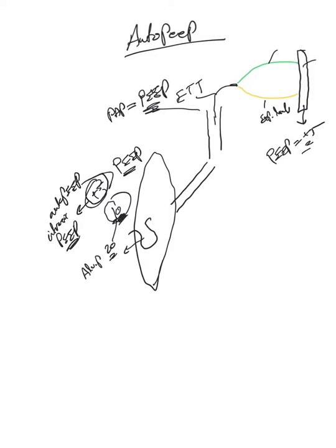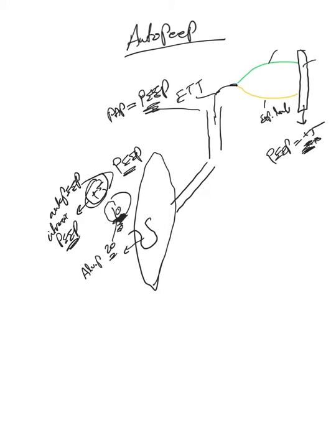So simply, the alveolar pressure now is 10, right, and the expiration terminated. And it's above the PEEP, the applied or extrinsic PEEP by plus 5. We need to allow the ventilator to sense and measure the pressure at that moment. How? Simply, you need to cease all kinds of flow and give a little bit of time for the pressure of the alveoli to be distributed and become equivalent all over the place.